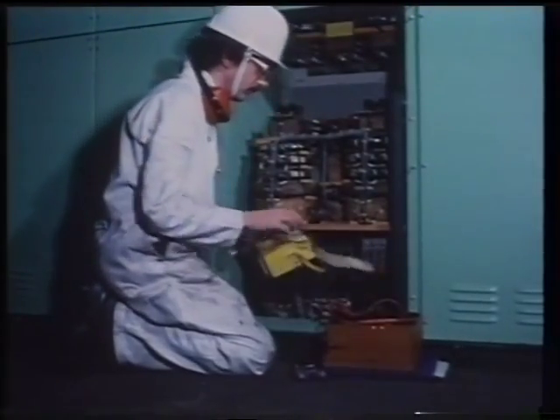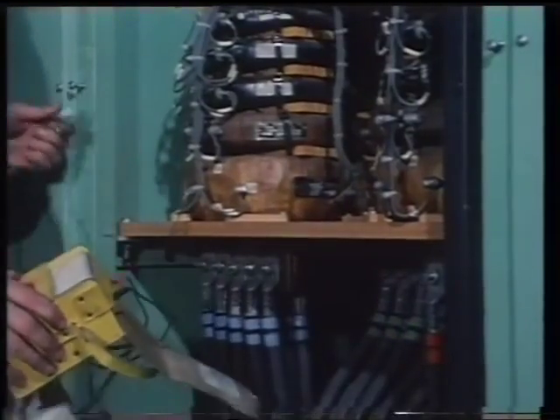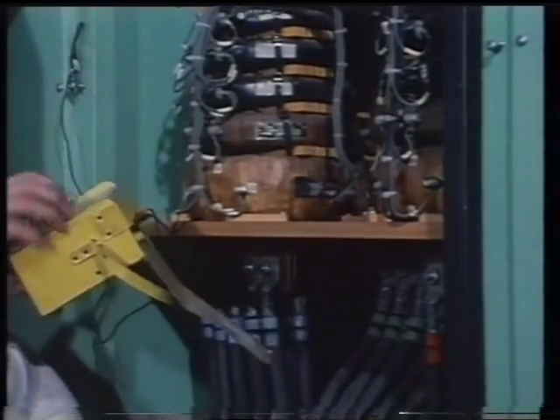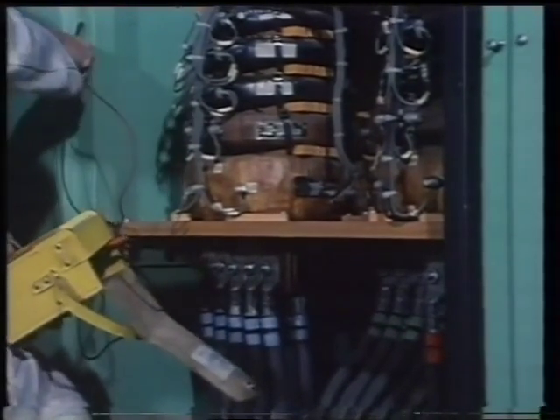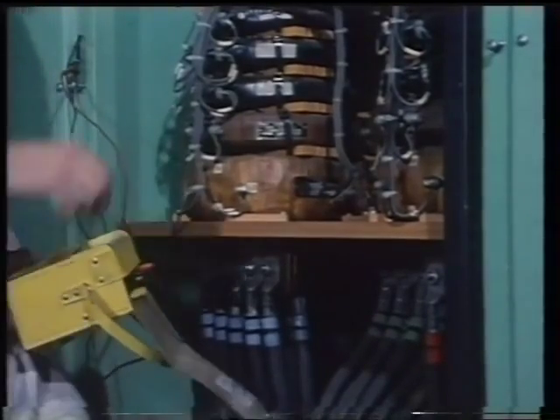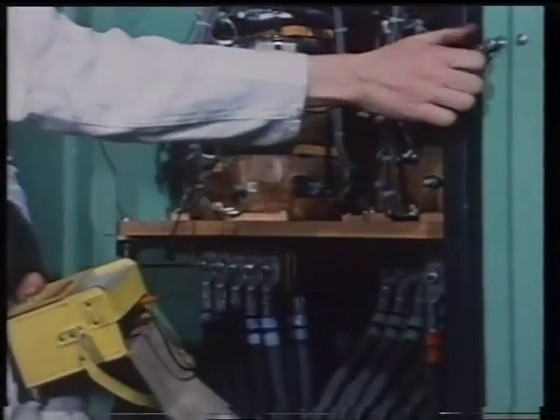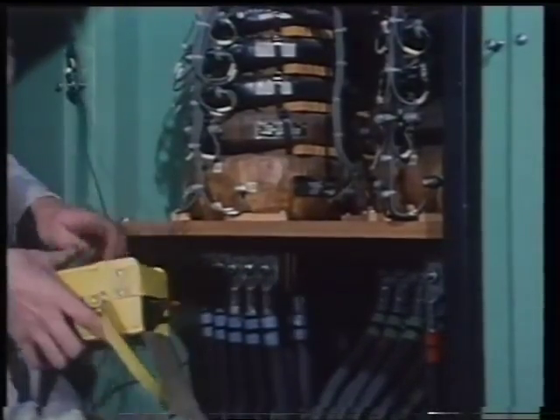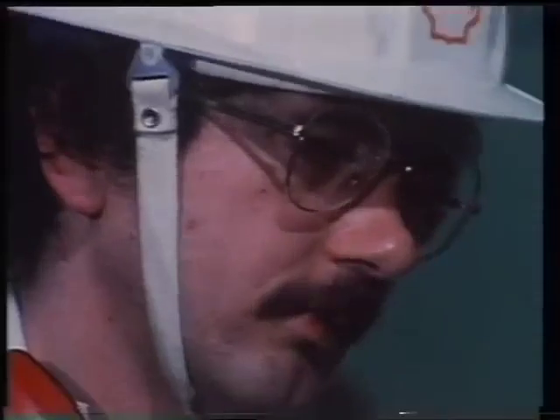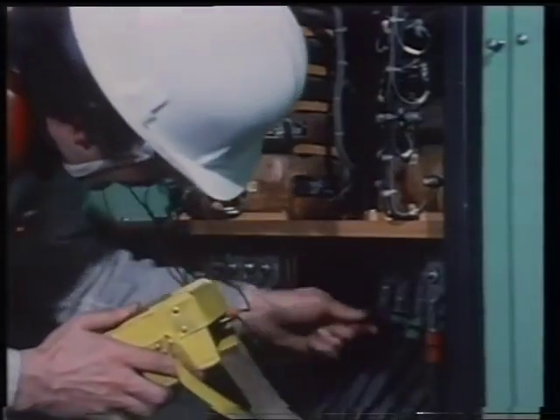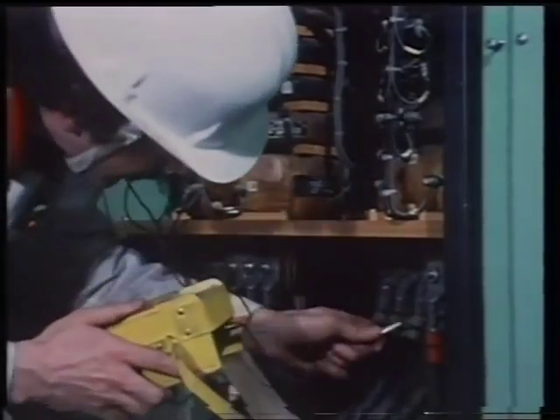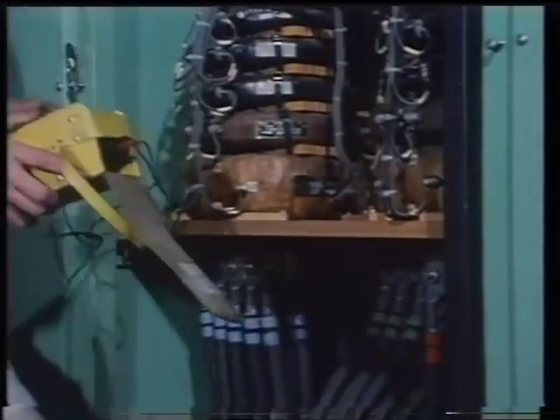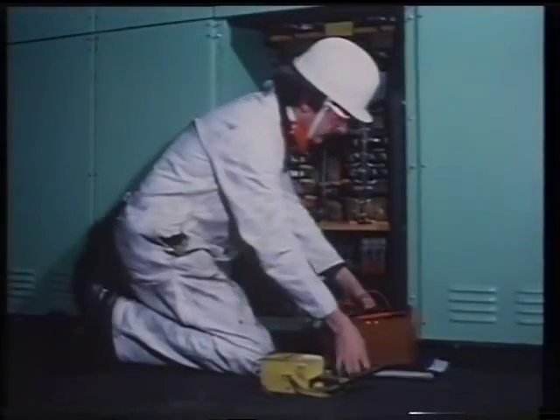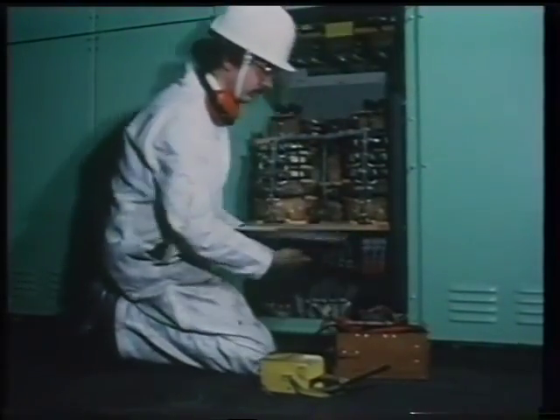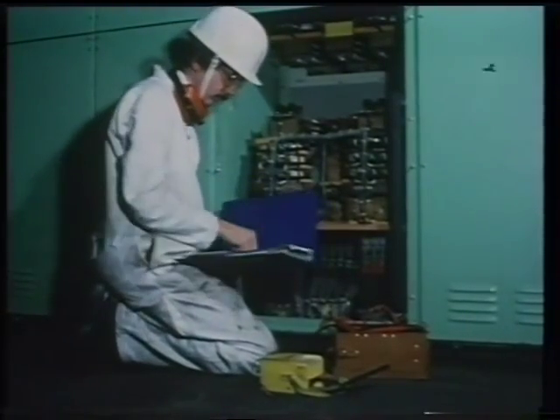Then the insulation resistance tester is checked. Two good earth points must be found. Then the phases can be checked to earth. If the insulation resistance values are checked, these can be recorded and the resistance trends monitored.